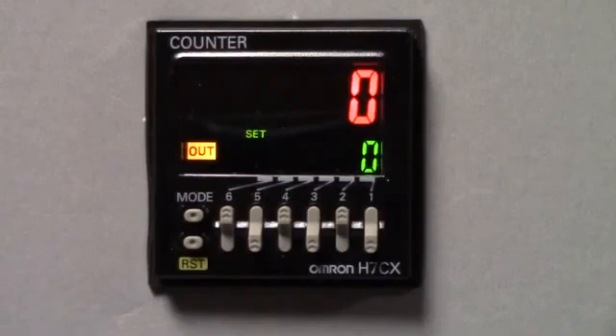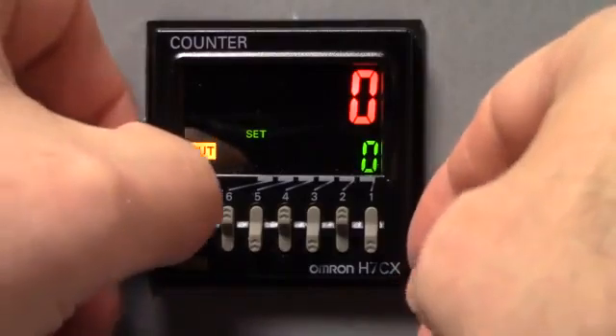So first, let's check our wiring to make sure that the unit is properly wired from an input perspective and also from a line voltage perspective. After doing so, power up the unit. Once you power up the unit, you'll see that the process value is zero is red, and the set value zero is green, and then your output light will be on. And that's okay, that's where we want to be. That being said, so we need to get into the parameter setup, and by doing that, we're going to press the mode key first, and then the number one key.